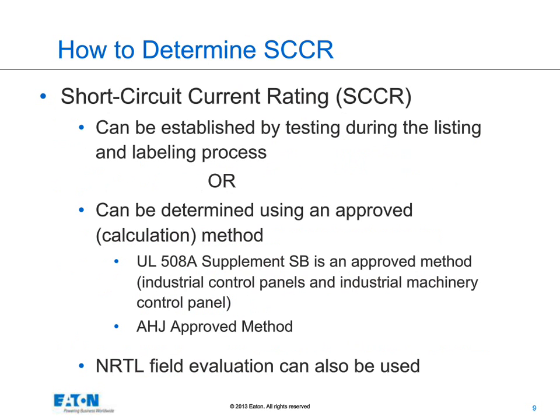How do we determine the SCCR for equipment? The first method would be to actually test the equipment. However, for a lot of custom equipment, testing is not really an option. So the vast majority of equipment, especially industrial control panels, would be determined by the approved method — UL508A Supplement SB. There is also an AHJ-approved method, so the 508A method is typically what's being done. If you have existing equipment and are looking to comply with OSHA requirements for proper SCCR, you might look at a field evaluation from a nationally recognized testing laboratory, such as UL or ETL.